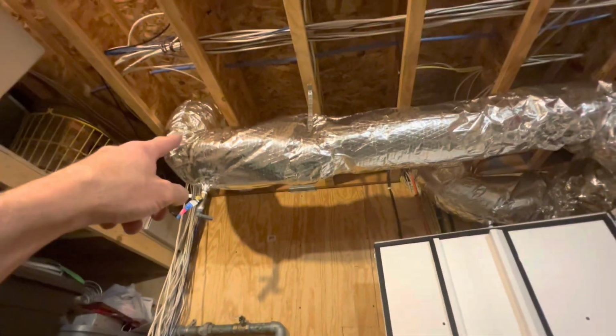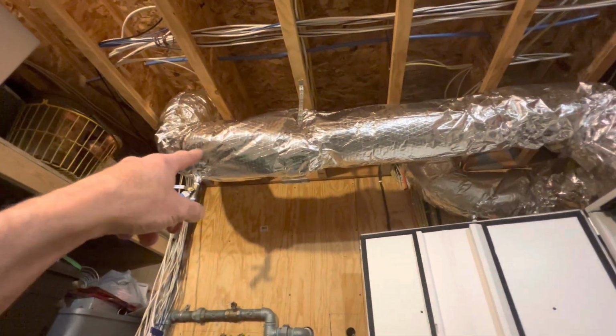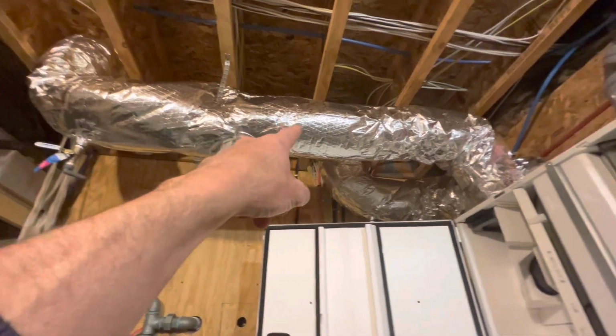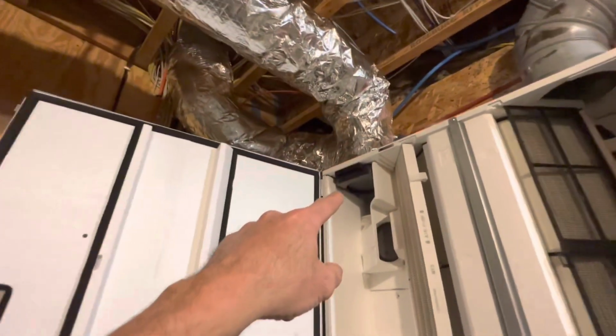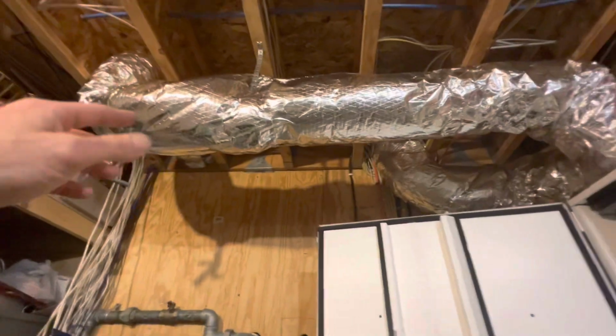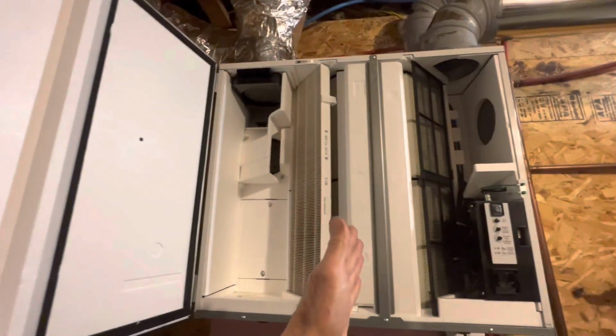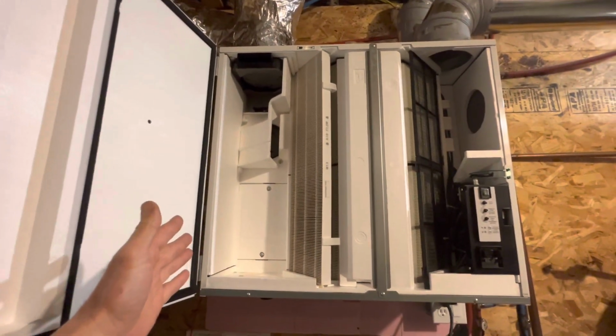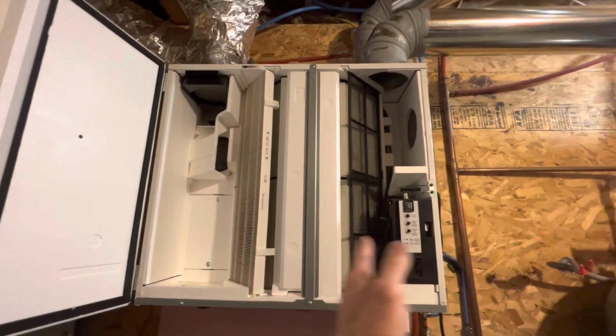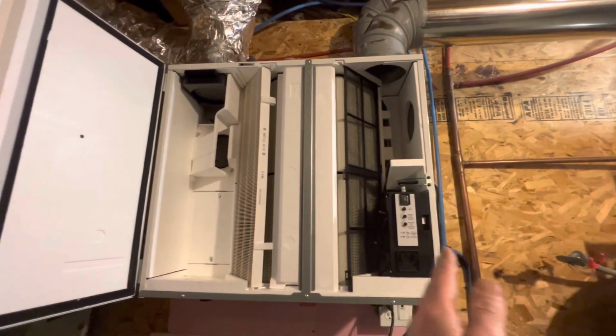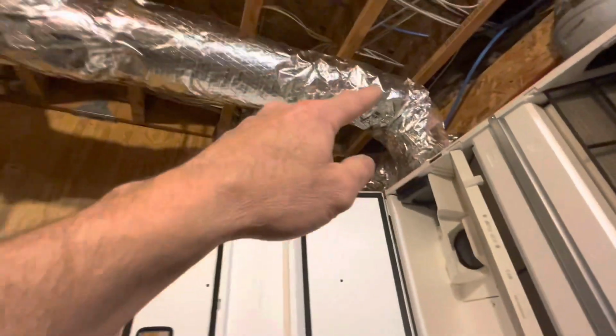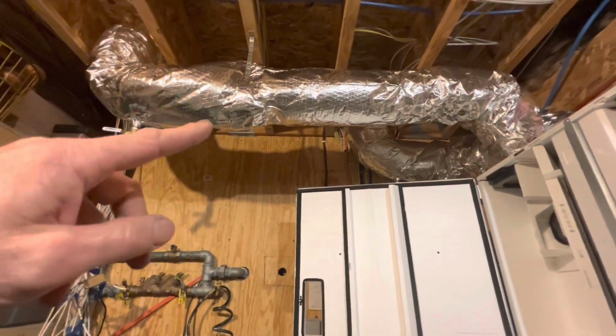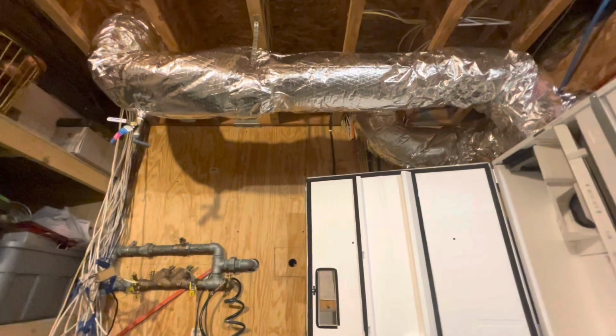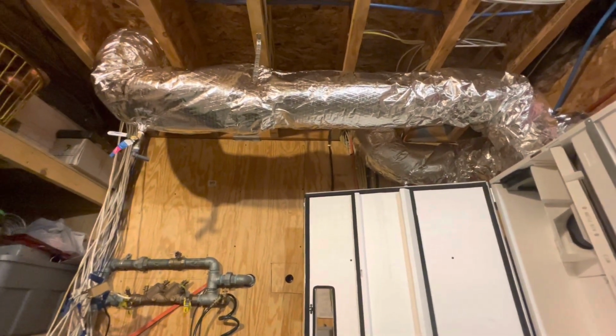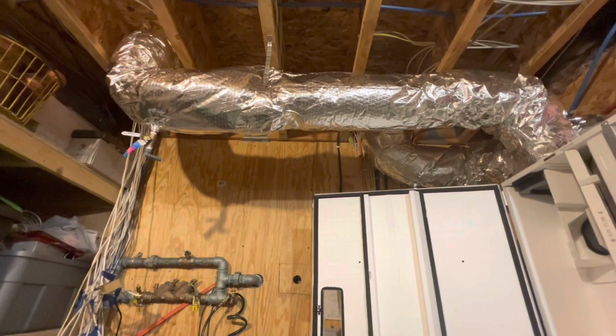So, like I said, this line here is my fresh air supply being sucked into the ERV for my cold side. Essentially, the cold side is everything on this side of the ERV. The hot side, the warm side, is everything on this side of the ERV. So for my cold side outside ductwork, I used drain, waste, and vent 6-inch PVC. Inside, I insulated that ductwork.